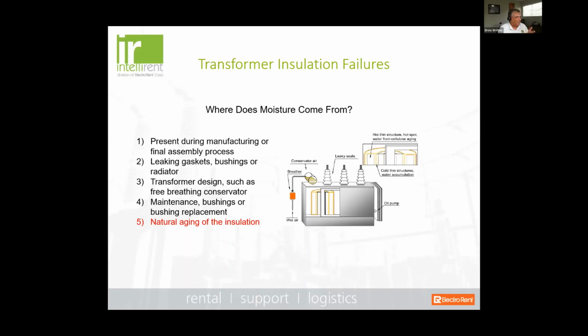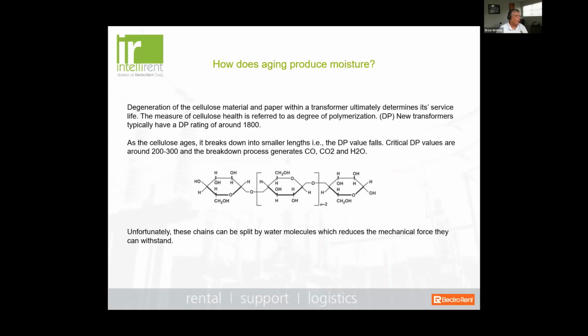You have leaky gaskets around your bushings or your radiator, or even the transformer design, such as a free breathing conservator with a bad desiccant, can absorb moisture right into the conservator tank if you don't have a nitrogen blanket. But I think the most important thing to understand is that moisture accumulates from the natural aging of the insulation. And how does this happen?